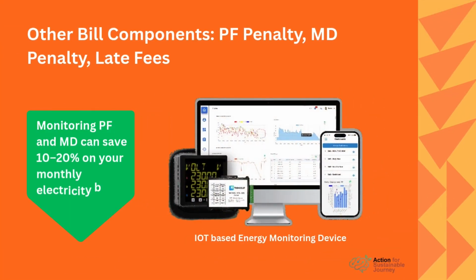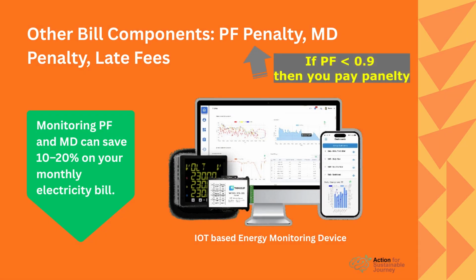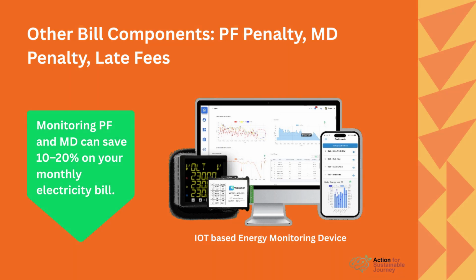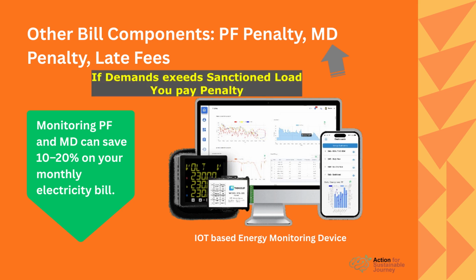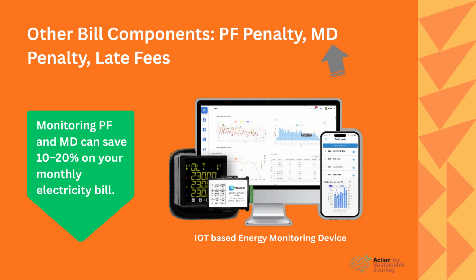Some hidden charges can increase your bill. The first one is power factor penalty. If power factor is less than 0.9, you pay extra. Using capacitors improves power factor. The second is the maximum demand penalty. If demand exceeds sanctioned load, penalties apply. The other one is late payment charges.